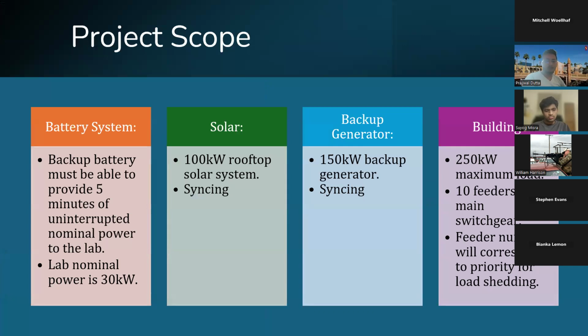The project here focuses on designing the microgrid system that can maintain power to a critical research environment. The primary parts are the battery bank that we designed to deliver 30 kilowatts for 5 minutes of uninterrupted power, a 100 kilowatt rooftop solar array to reduce loading on the utility grid, and a 150 kilowatt diesel powered generator to maintain long term power during an extended outage. The system also has automated load shedding for 10 feeder breakers to make sure that the critical loads are prioritized, and real time automation for seamless transitions between power sources.